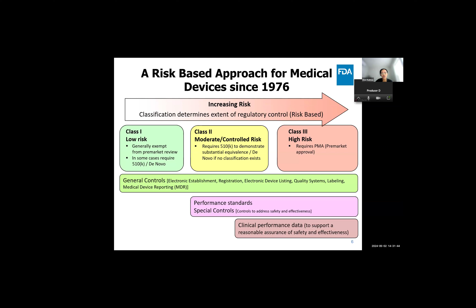We recommend that you start interacting with us early on, prior to starting your clinical study, so that we can give you feedback on your clinical study design approach. You're able to do this through Q-subs. There are different types of Q-subs. A pre-submission, for instance, is one where you would submit your questions to us and you could get written feedback from us. It provides an opportunity to interact with us early on and discuss your intended pre-market submission. We don't do a pre-review of data in a Q-submission, but rather give feedback on your approach. You could be asking us about a clinical study that you're designing, or it can be an informational meeting, where you share information with the FDA without expectation of feedback. Those are called informational Q-subs.